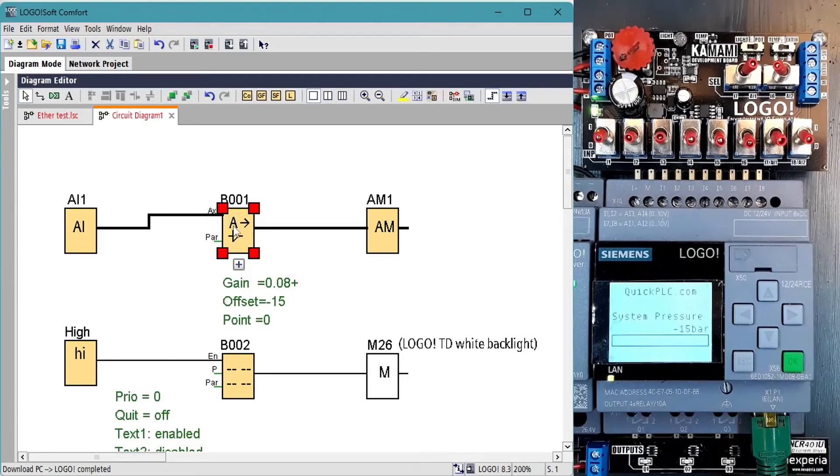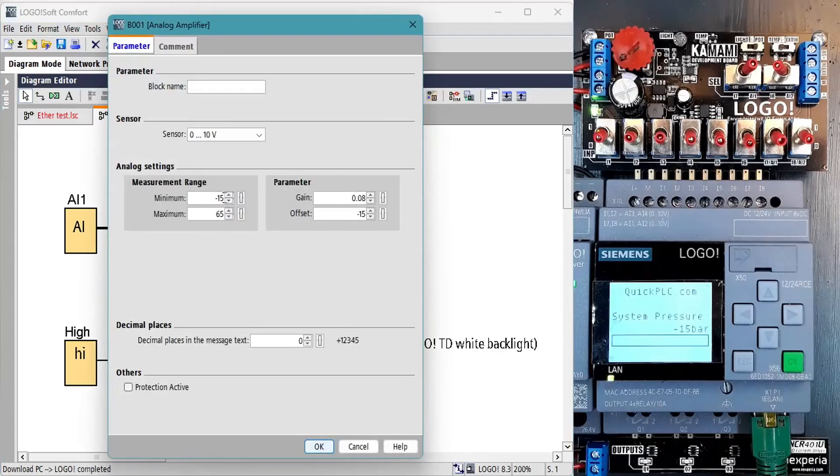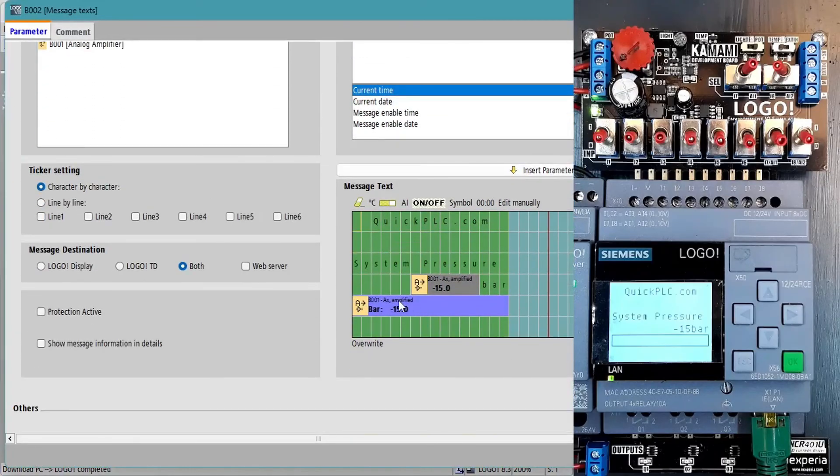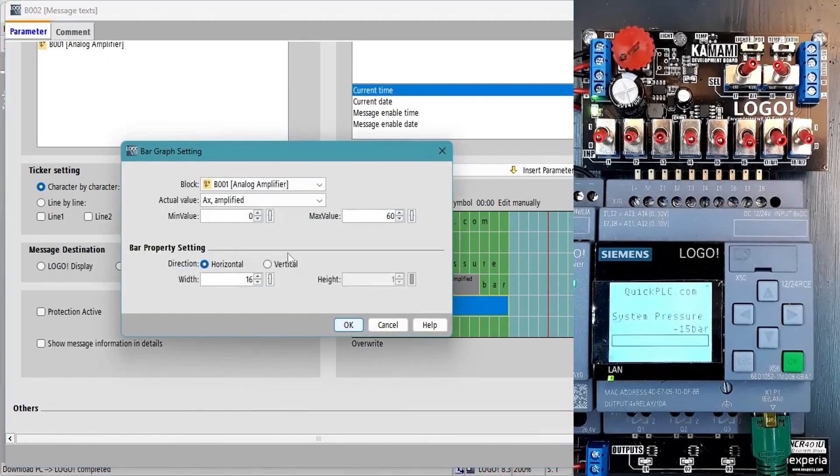While we're on the topic we'll modify to display the reading to one decimal place. We set the decimal places in the message text to one but all that does is add a dot so that 60 becomes 6.0. We need to scale the measurement range by a factor of 10. Watch the gain and offsets update as we do. The message text will automatically update the digital readout but we need to rescale the bar graph which doesn't know about decimals. It will see the 600 come through at full scale. That's done so transfer to the logo and test.